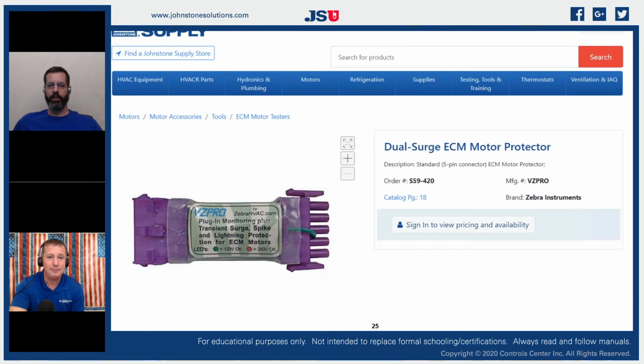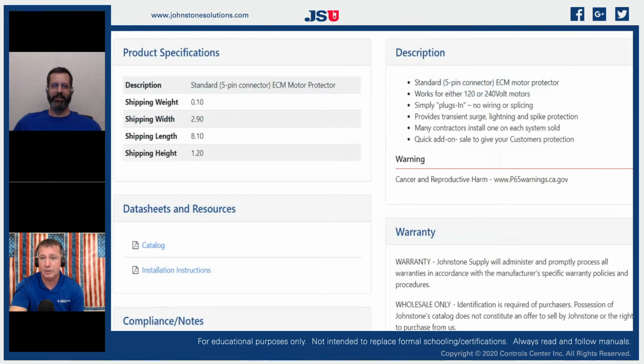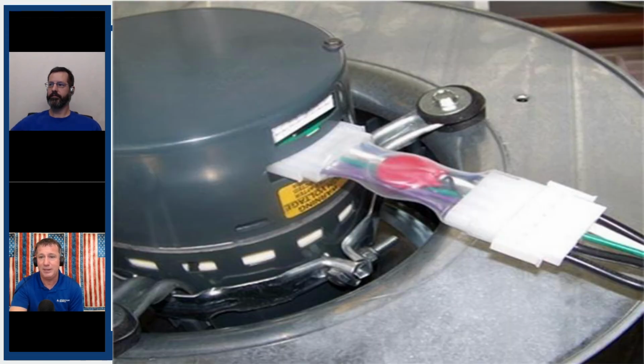When I was in the field, we installed those on new equipment. We would install it, especially when it was rural and in the country, or if the house had a whole house standby generator. For sure, that'd be a great place for one, because when that generator fires up, I guarantee you're going to have some voltage changes. So great little piece for the money too. They're not super expensive, and it is that standard 5-pin. It's good for 120 or 240 systems, so it works on gas furnaces or air handlers, either one.